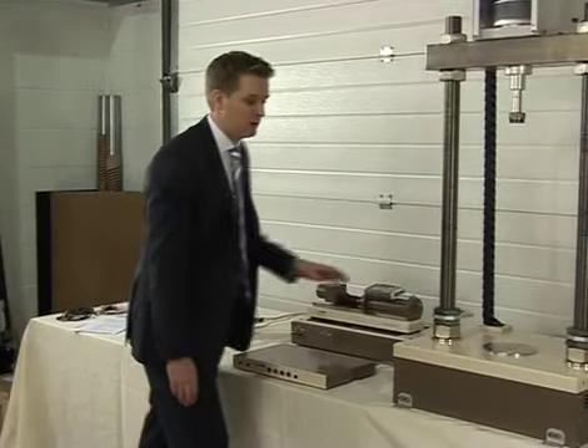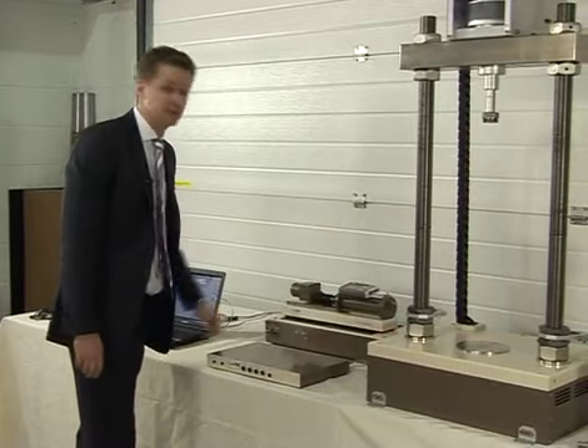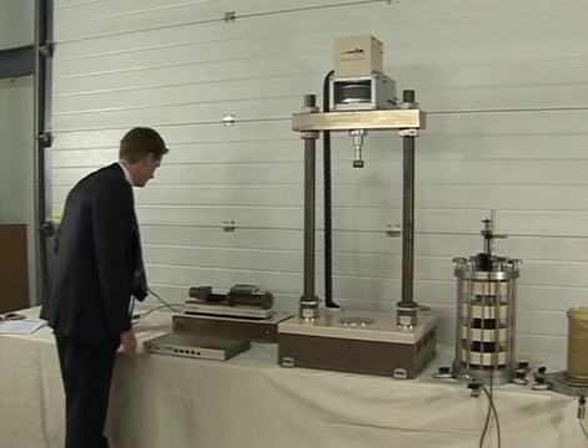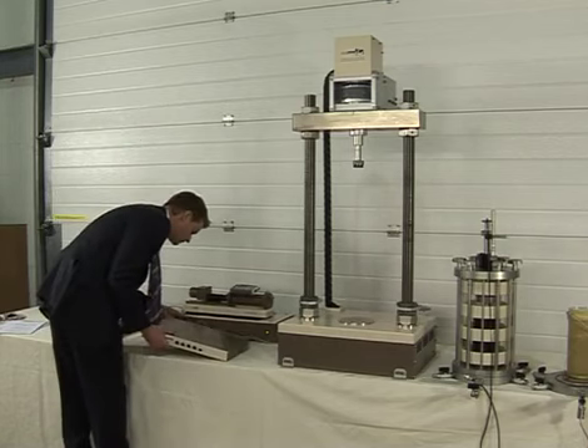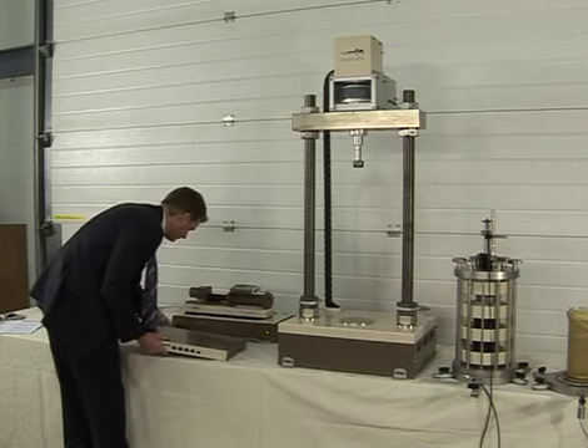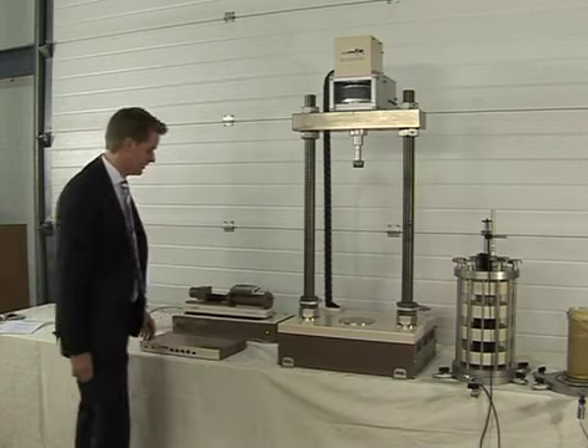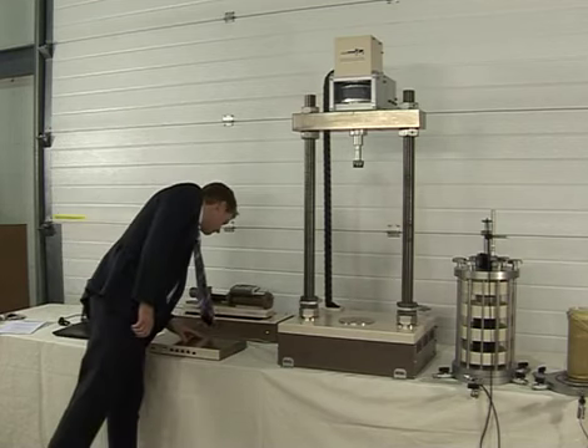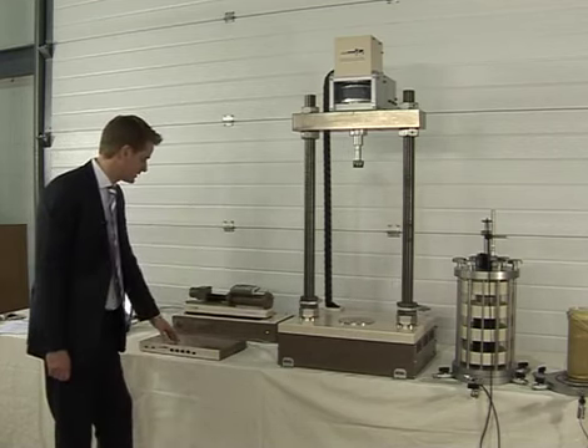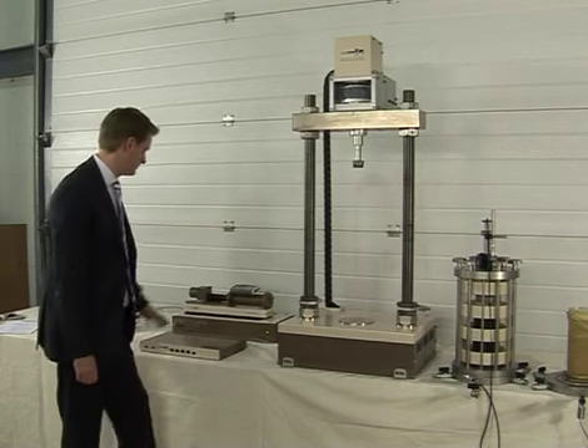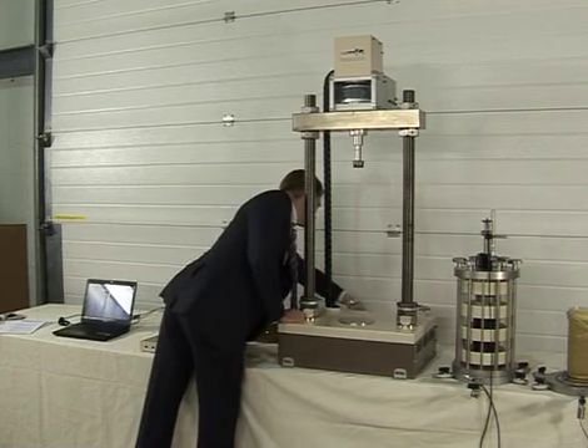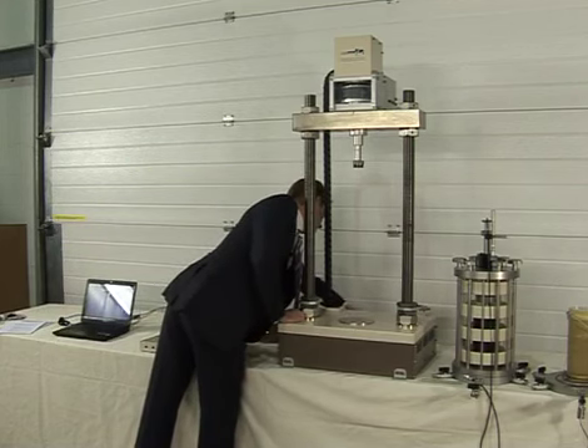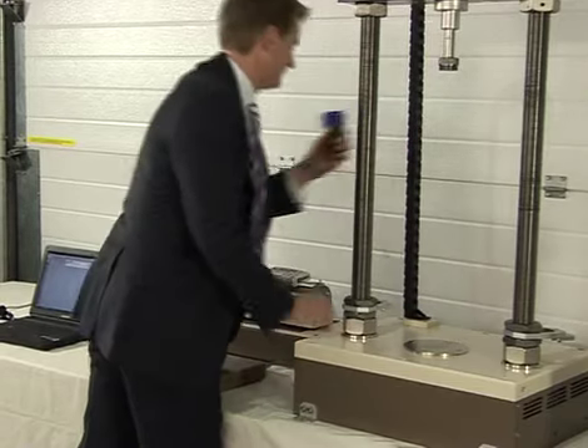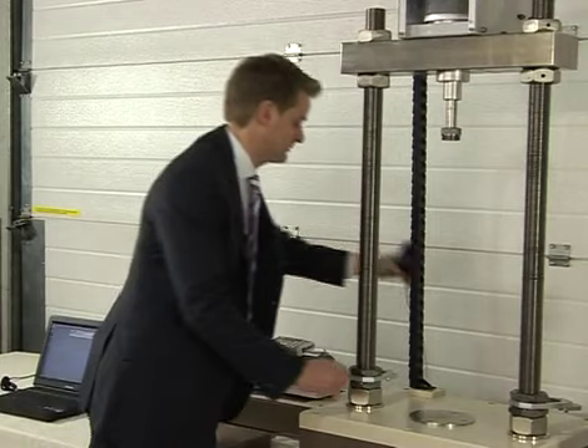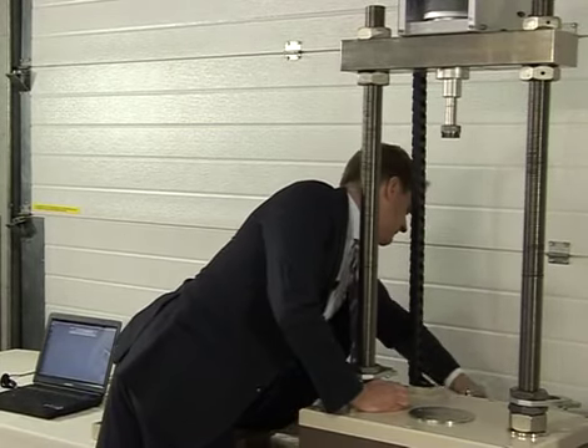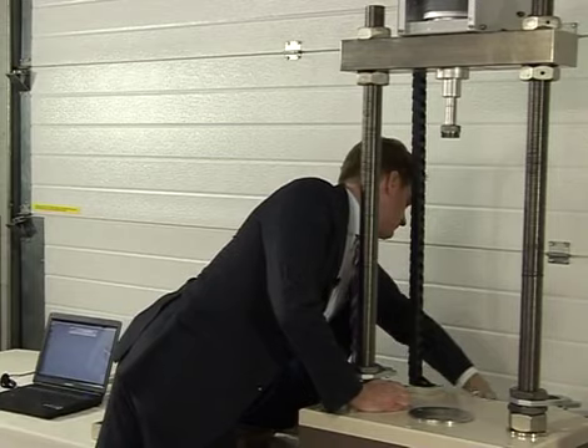Now we need to ensure we have power to both the load frame and to the DCS control box. So we have a normal IEC connector, which we will connect to the back of the DCS box. And I won't switch that on just yet. It runs from 110, 115 volts or 220, 240 volts, so you should have no problem there. And then the main load frame has a large connector for the power, again at 110 to 240 volts, which connects into the back, like so.